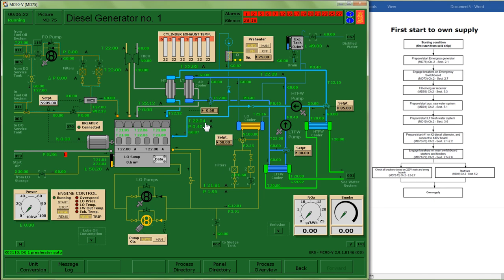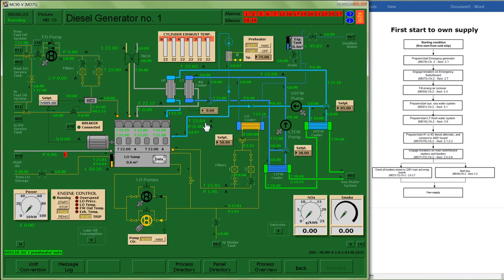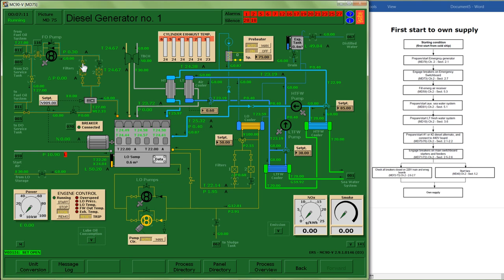Our fuel system we're going to start from our tank that we're going to pull fuel from. It's over on number 5, it's our diesel oil service tank. I've got an emergency shutoff valve from the tank as well as a supply valve to the diesel generator. And if I continue through my pathway I have a shutoff valve, a pump, and then a series of filters. You'll note my pump is not running. I can't activate it. The symbol shows that it is a shaft and pulley driven pump, which means that it's going to be driven by the rotation of the engine.